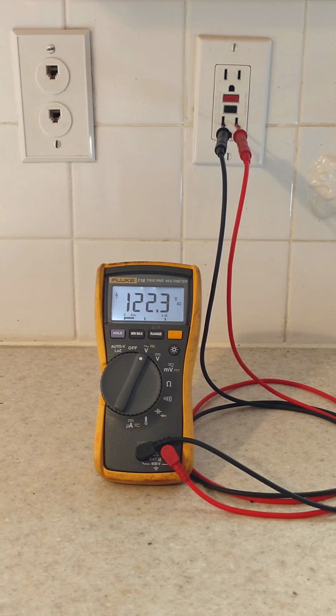In my case, that was because I had disconnected my probe from the outlet. But we would see the same phenomenon if the wiring in the wall was disconnected from the outlet, or if the receptacle to wiring connection was okay, but there was a break between the wiring and the circuit breaker for that circuit. Those would all show up as ghost voltage, and they would all tell us that we had an open neutral, and that's what's key.